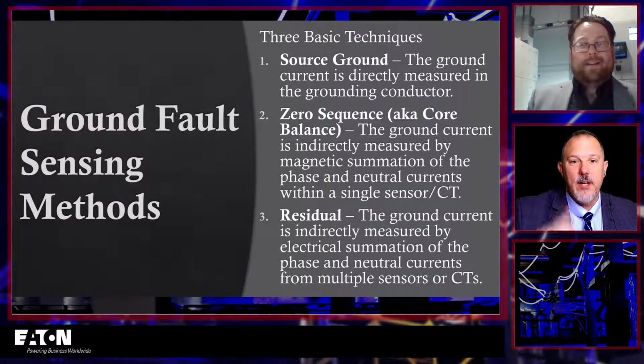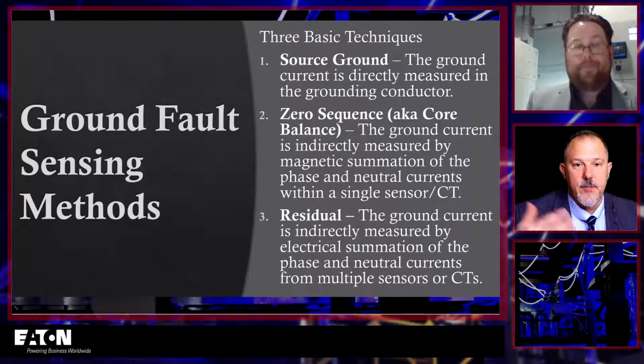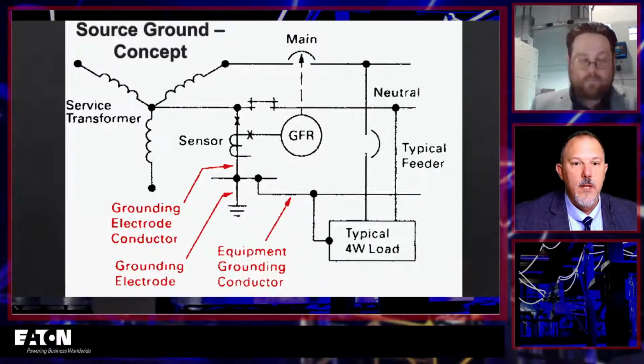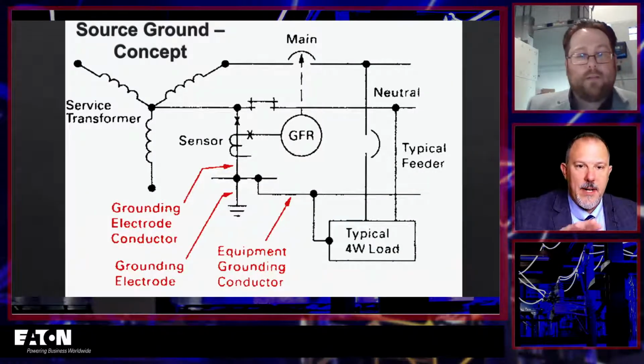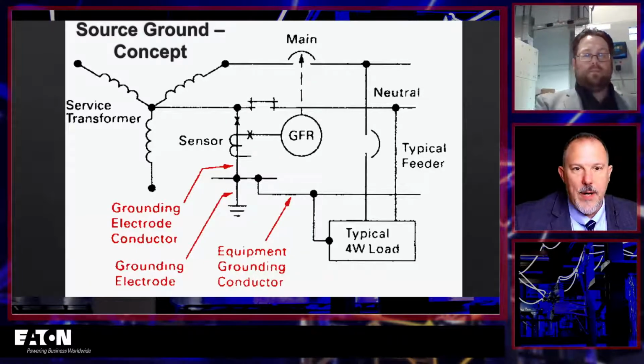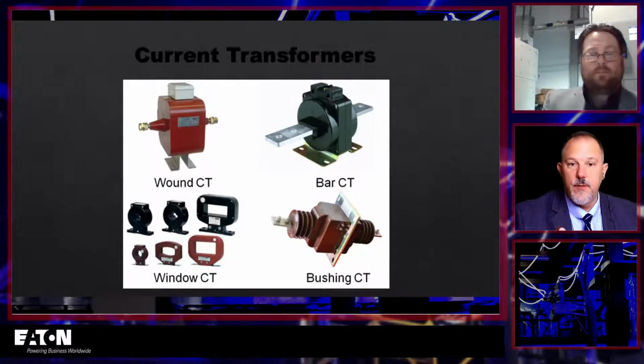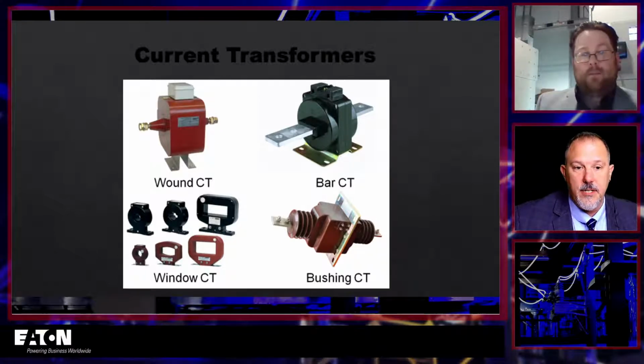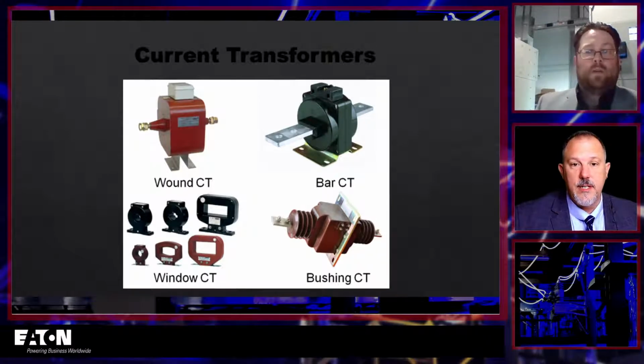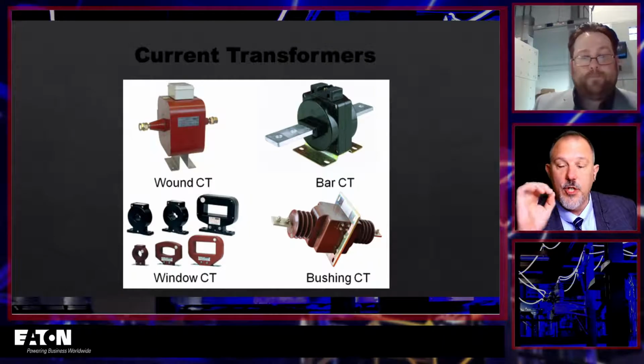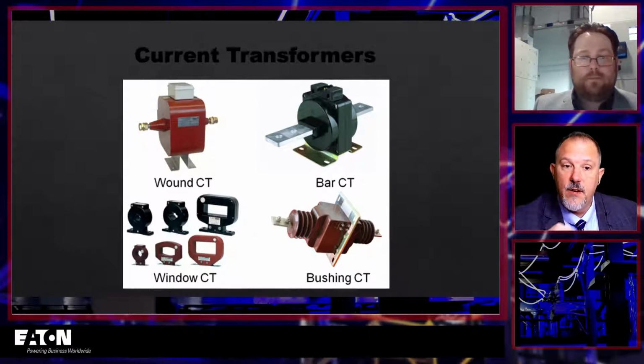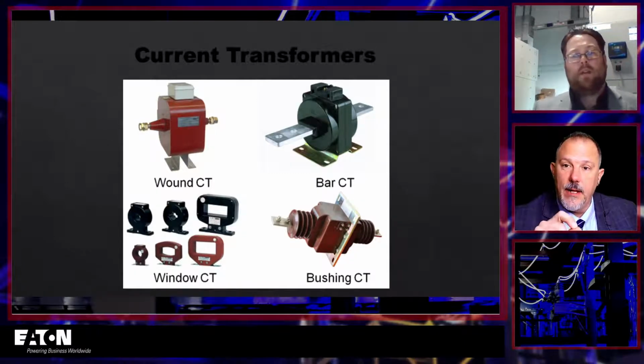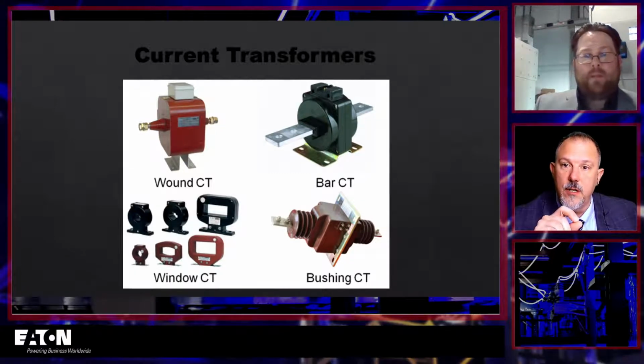So we covered these three things: zero sequence, source ground, and residual. We talked about the different components, the grounding electrode conductor, and how it's wired makes a difference. These are different types of CTs, so you've got your window CTs and your bushing CTs. On these, what you would do is verify the turns ratio. And how do we determine the phase ratio?